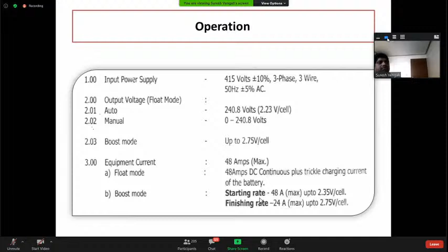So why constant voltage charging? Because the battery is in healthy condition, so you don't need to charge the battery, your main criteria is to supply it. So your cell voltage is in float condition at 2.25 volts. If you want to quickly charge it, you move to boost charging, which is the constant current method, charging at a high rate to quickly complete the charging. These are the charging methods we use. This is internal only, you may not see it, you just press the button for float or boost.